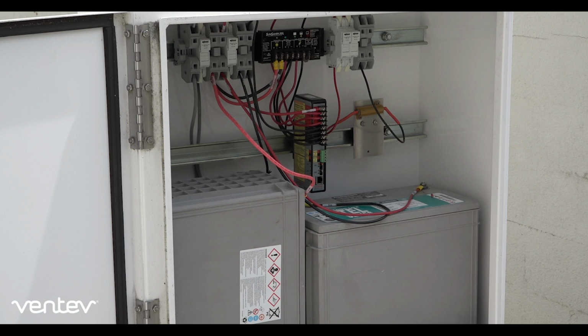You can also set up SNMP traps, so that if my voltage is low, the system will catch that and send you a notification that, hey, your battery is low. This also allows us to test the batteries. What's unique about this system as opposed to other systems is it will actually test under load. It'll shut down the solar panels and the charging to the batteries, and it'll run the test while the load is being powered.